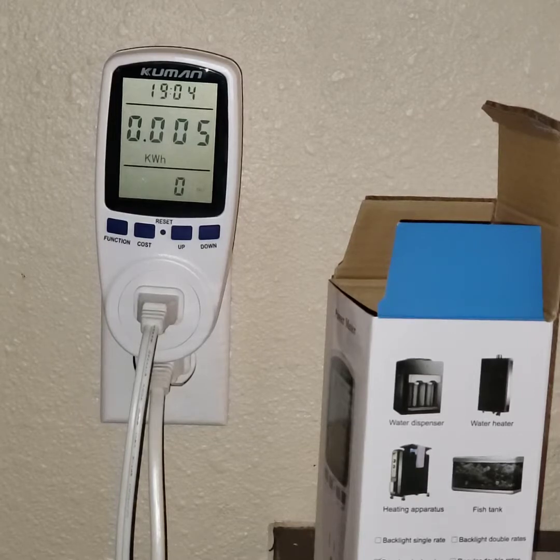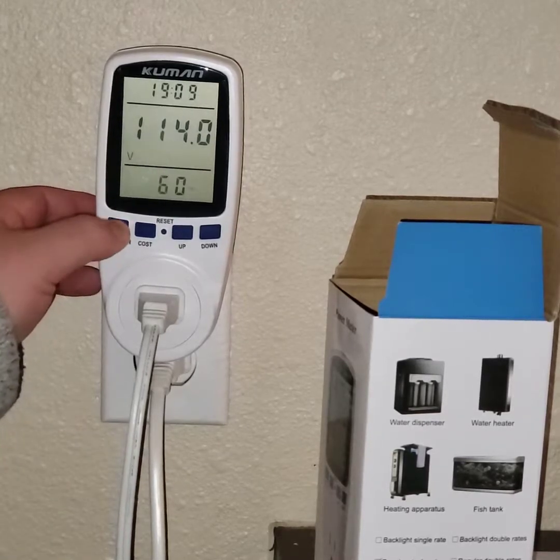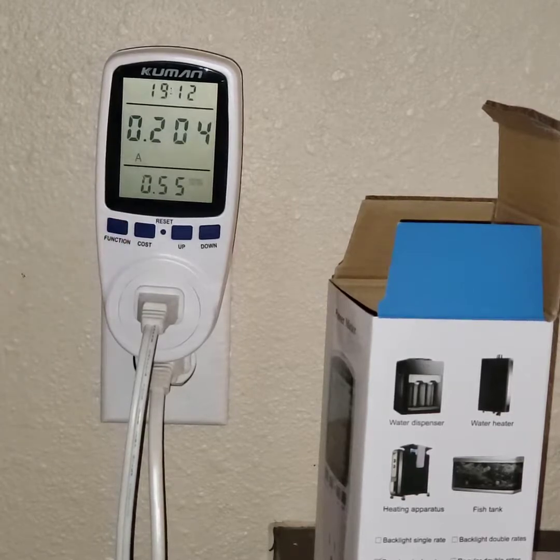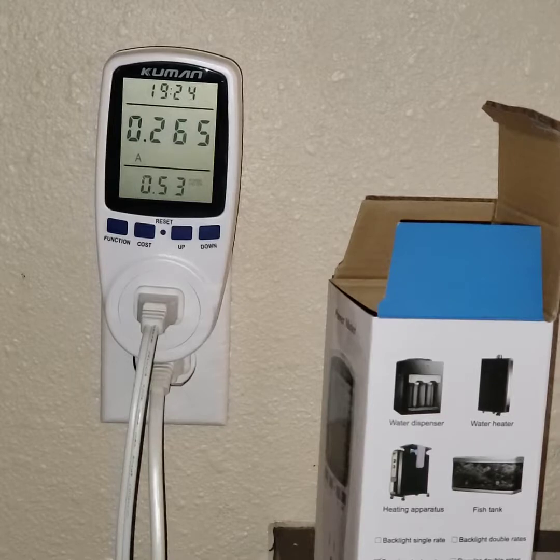It's what I'm looking for — a simple way to check what's going on. So now at 0.20 amps, I'll turn it off and switch to the higher speed on the fan. There you go — 20 amps up to 0.27. That's the higher speed, so it does make a difference, about 0.065 to 0.07 amps more on average.